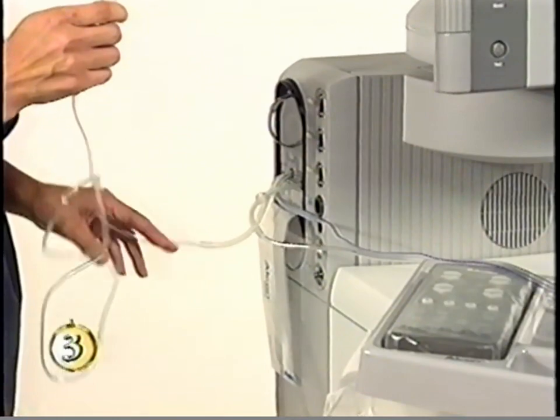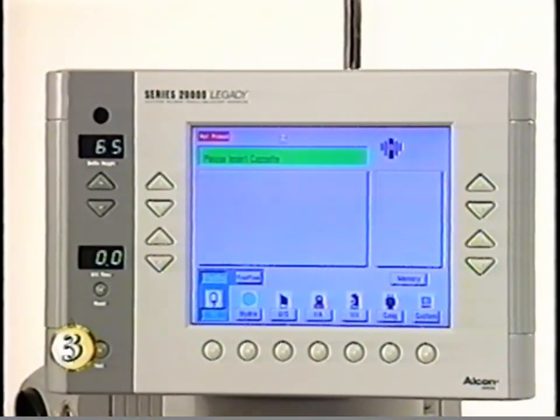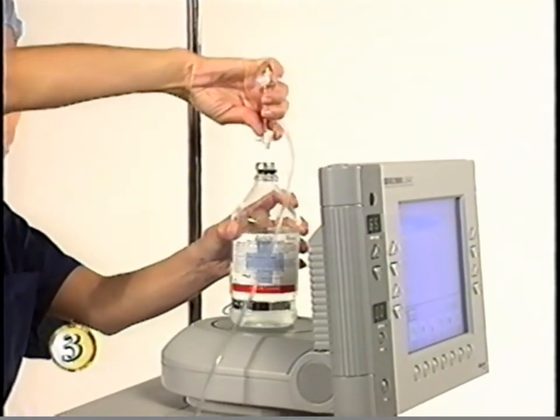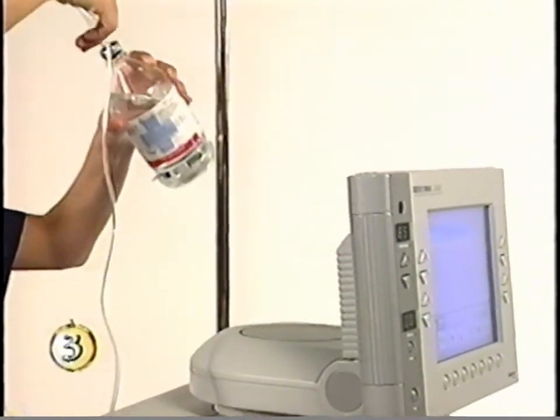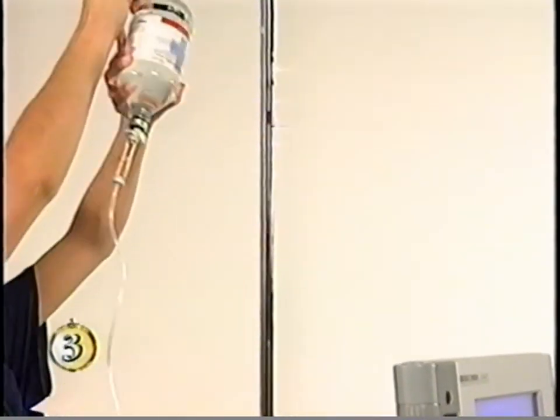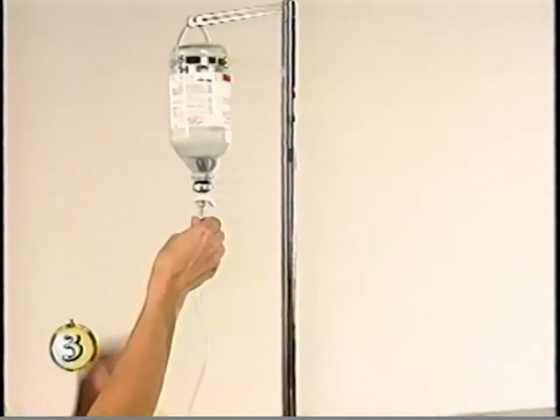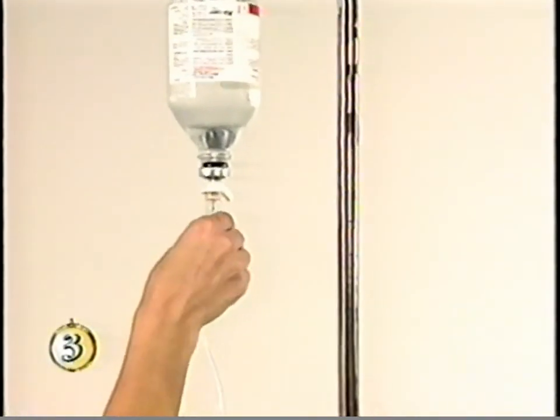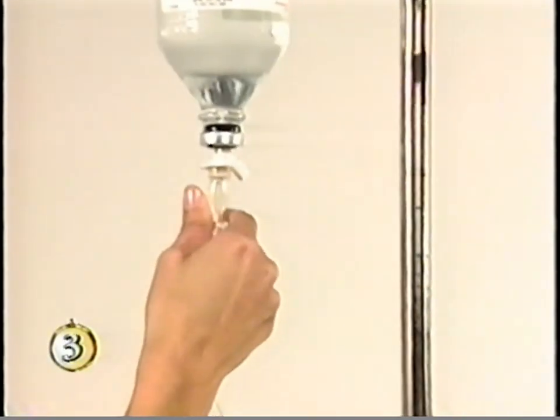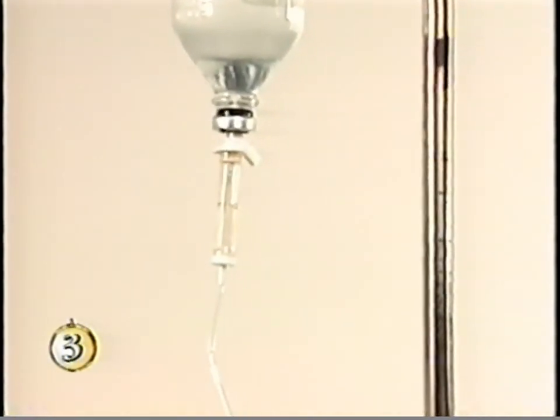The drainage bag should hang freely. When the cassette is inserted properly, the front panel cassette symbol will disappear. If it stays illuminated, reinsert the cassette or check the troubleshooting section of the operator's manual. Next, the circulator spikes the irrigation bottle and hangs it from the IV pole, then squeezes the drip chamber to fill it about half full. If the drip chamber does not fill, check for kinks in the irrigation line.